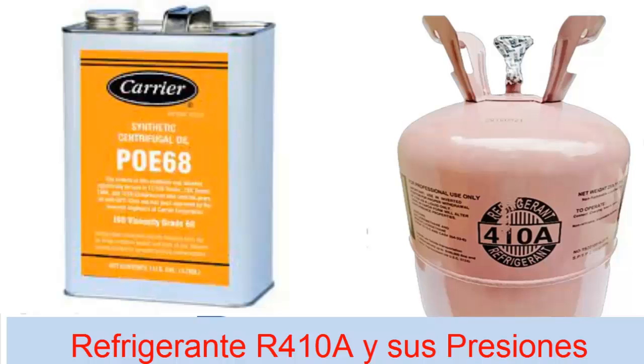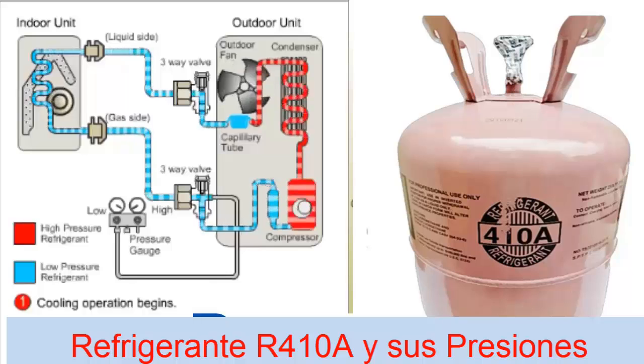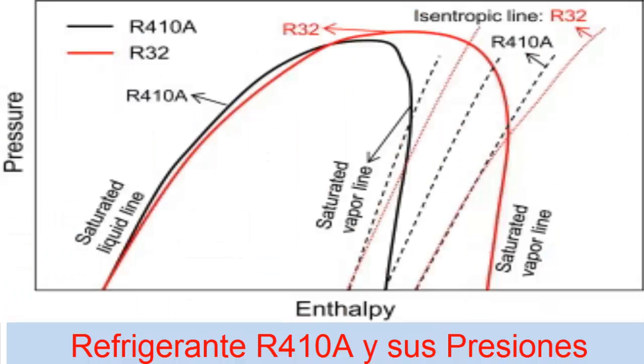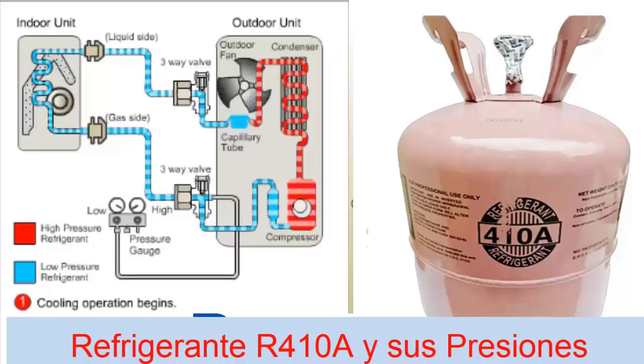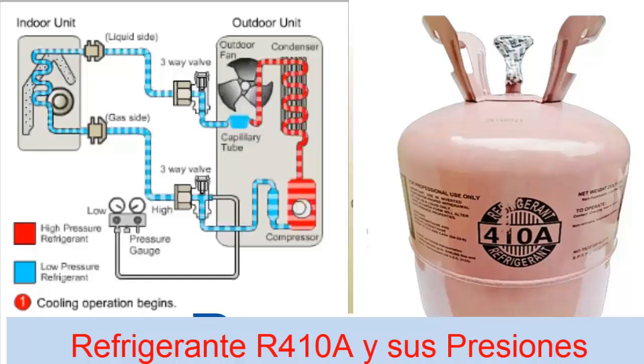That is why the R410A has less of a problem for oil return when compared to the R32. Regarding the compressor discharge temperature: the coolant enters the compressor at low pressure and exits at high pressure, and the temperature is a very important factor for the durability of the compressor. The normal discharge temperatures of the R410A are close to 80 degrees Celsius. Compared to R32, which goes above 100 degrees Celsius, the R410A's 80 degrees Celsius is much lower, which is very beneficial for maintaining the viscosity of the oil in the discharge.